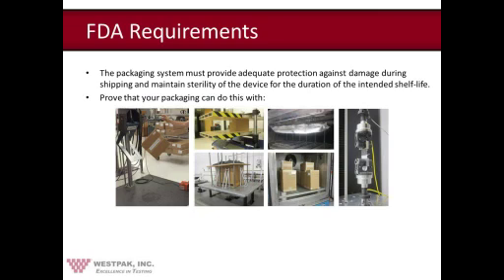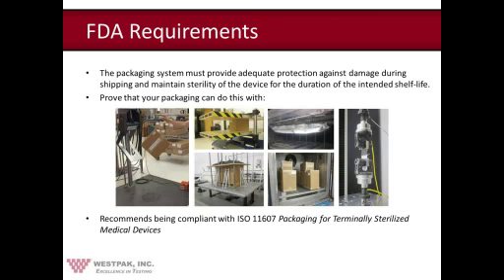So this should comprise your distribution simulation testing, your sterile barrier system integrity testing, and aging shelf life testing. But again, they say to do this, to prove this, but they don't provide too much guidance on exactly what needs to be done specifically.